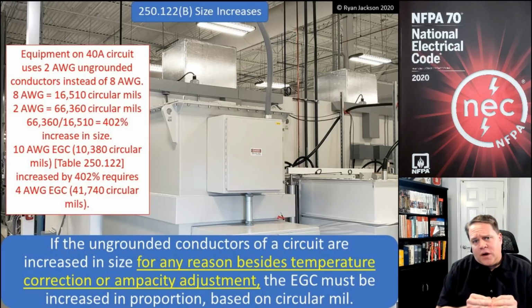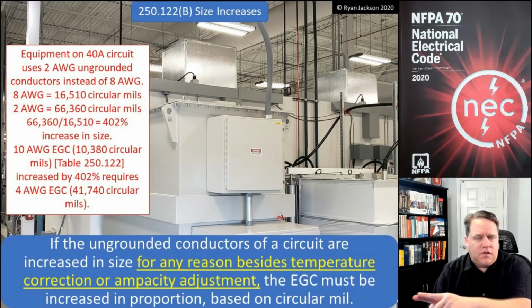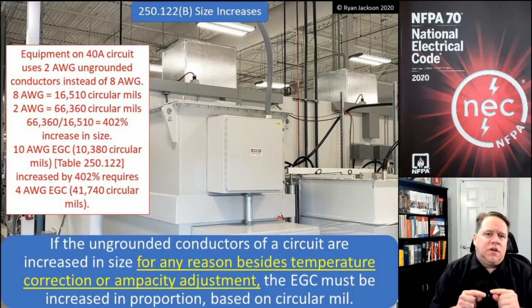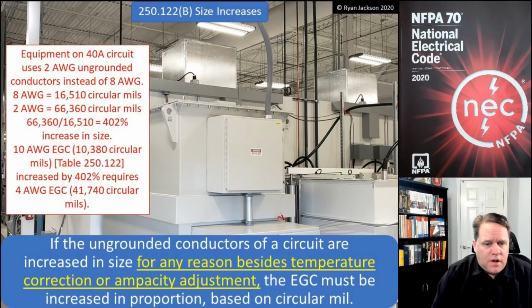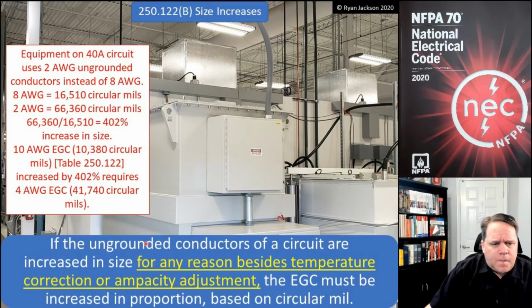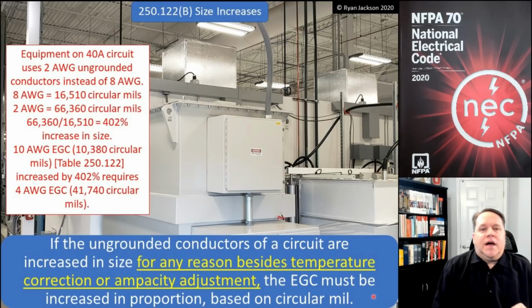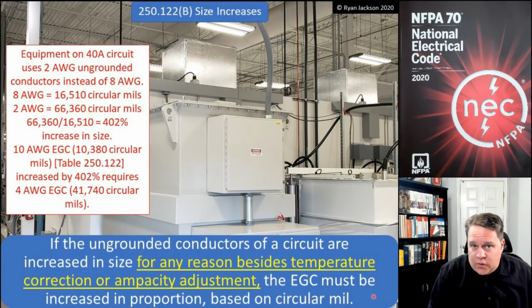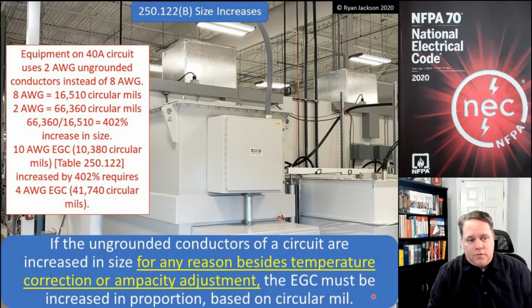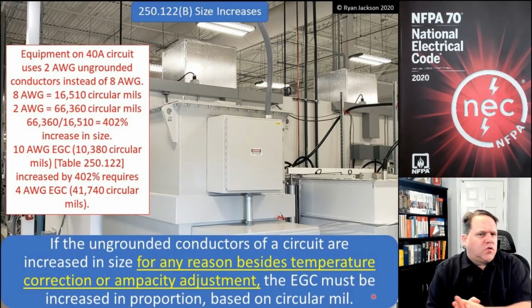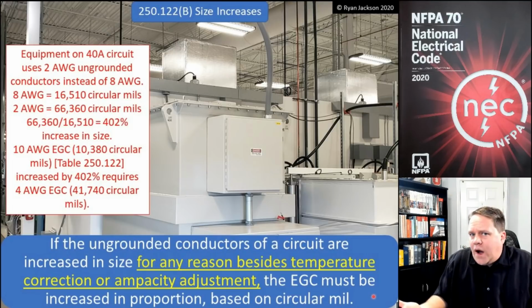So at some point, I do need to recognize that it doesn't matter why I increased the ungrounded conductors. I still have to increase the equipment grounding conductor in proportion. Now, if we look at the language again, it says if I increase them in size for any reason besides temperature correction or ampacity adjustment. Okay, so if I've got 6 conductors in a conduit, or if I'm installing my wires in a high ambient temperature, and I had to make them bigger, well, is that really an increase in size? No, that's actually the minimum that would be required, isn't it?